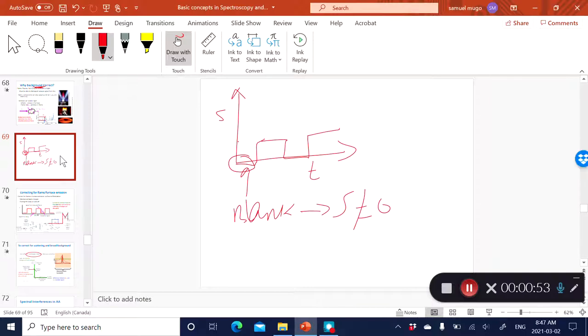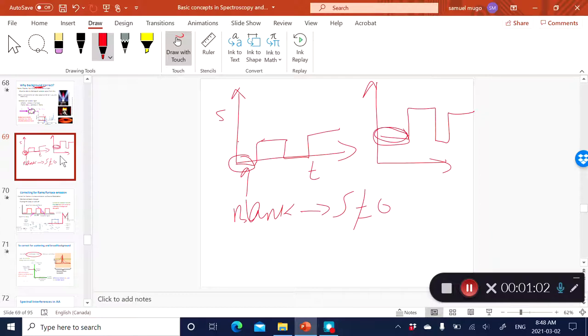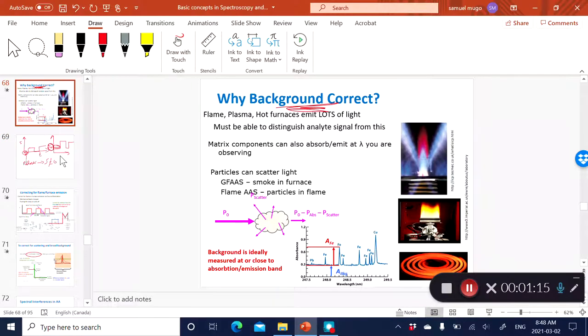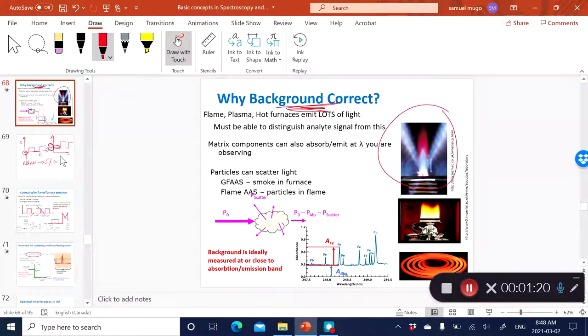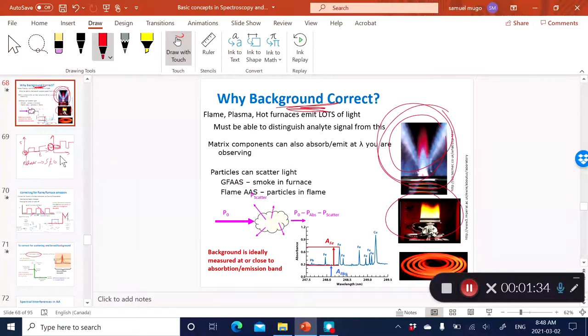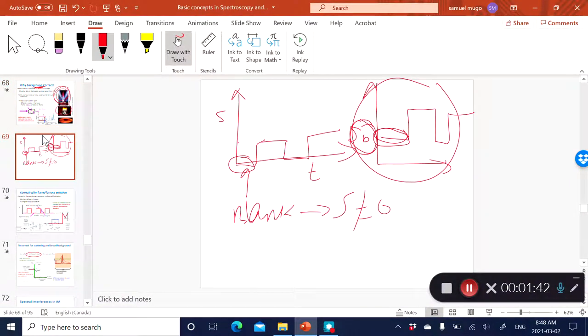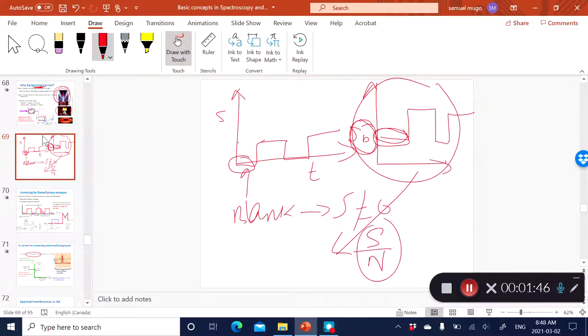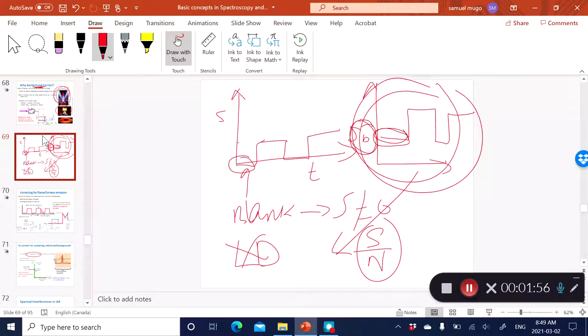However, in real life, when you're running the blank, there is still a little bit of signal related to the blank. This signal often comes from effects of the laser or light source, from the flame if you're dealing with AAS, or from the plasma if you're dealing with ICP. This situation affects your signal-to-noise ratio and therefore your limit of detection. So as an instrument manufacturer, you really need a way to correct for background in your instrument.